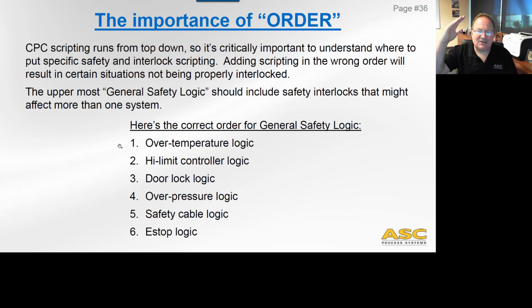So the uppermost general safety logic should include safety interlocks that might affect more than one system, and it should be in the following order, okay? And it's very important that you put your general safety in this order and this order only, okay? The main reason is that safety cable logic and e-stop logic will take active control of corrective actions, and these up here will actually turn those off. So we want to make sure that the hierarchy is these are the lesser general safety topics, and these are the more important ones. So the more important goes at the bottom.